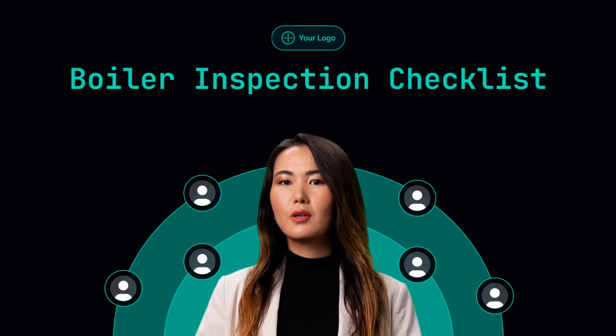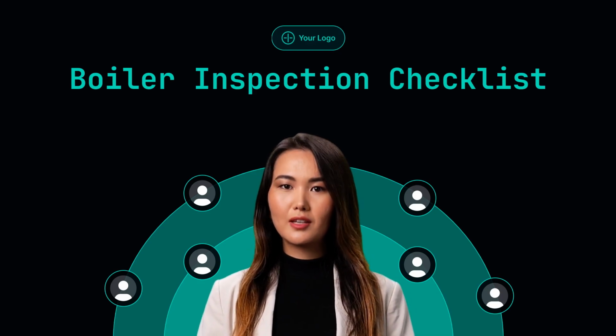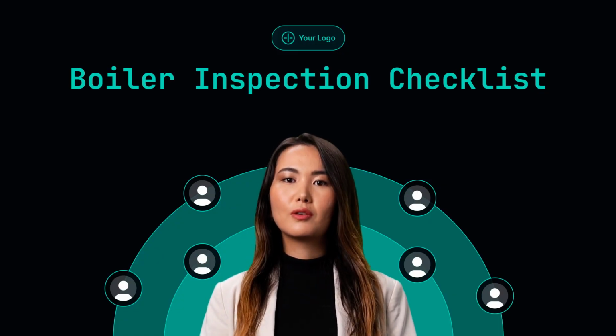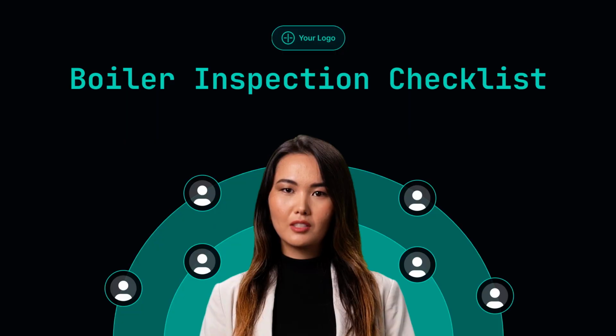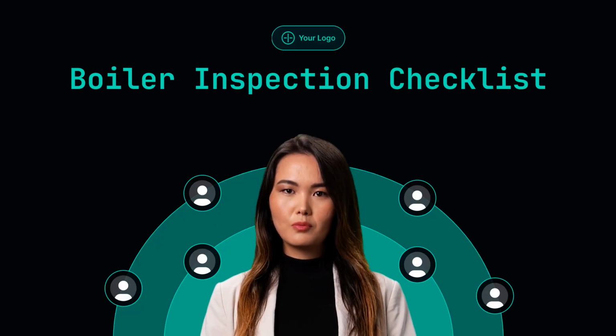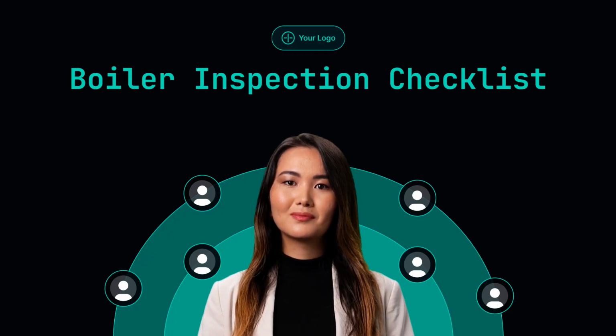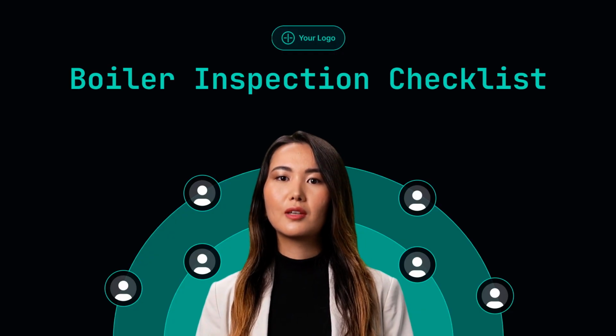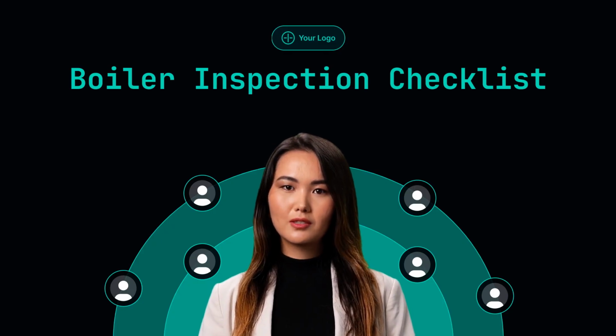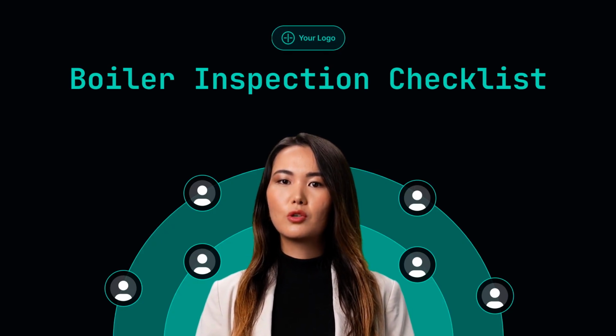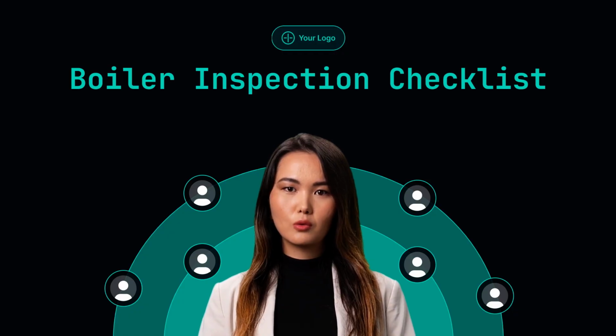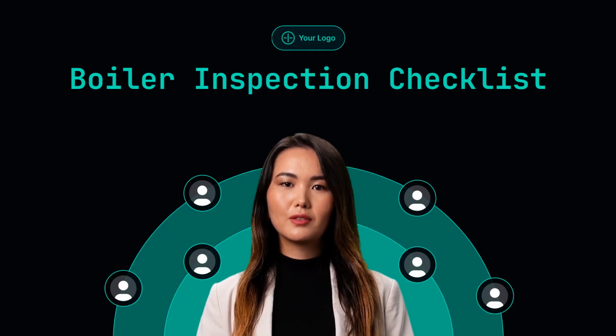Record facility name, location, inspection date, inspector name, boiler type, model, serial number, and operating hours. Check for visible leaks or damage, ensure gauges operate correctly, and inspect burner flame color and consistency. Verify water levels, test low water cutoff devices, check boiler pressure, ensure pressure relief valves function, record water temperature, and inspect fuel levels and lines.